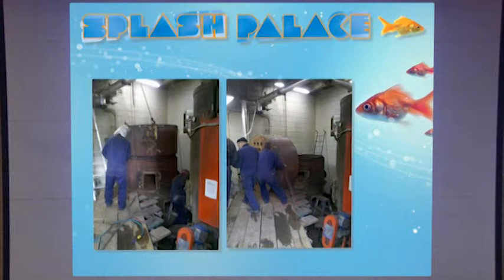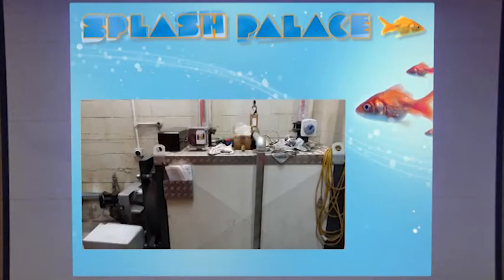So the first thing we did was remove the old boilers, and you can see us slicing this sucker up because we actually couldn't get the old boilers out the door. So we cut them into small pieces. This is a photo of the diesel backup boiler that had gone on. This is a relatively newer photo, and it shows we've installed this GSM modem here and a motorized actuator. So that automates a lot of the standby and backup process if the wood chip boiler goes down for whatever reason.